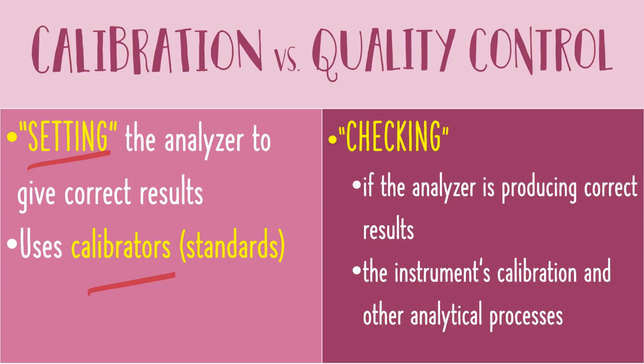Parang ni-reset niya ang inyong machines in the laboratory. Meanwhile, quality control is actually checking if your instrument is working properly. So that is mainly by analyzing if your instrument is producing the correct results, and to check if the instrument's calibration is right, and also other analytical processes. So mainly, if your calibration is resetting your machine to give correct results, then it is quality control that is actually checking if your calibration is done right, or if your instrument is calibrated properly.